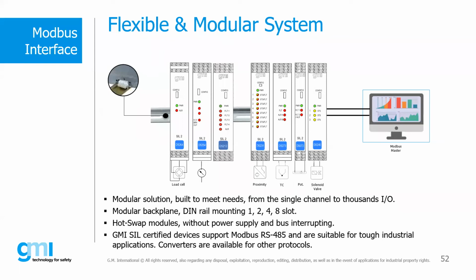The main reason for such high use of Modbus compared to other communication protocols is that it was designed with industrial use in mind. It's an openly published and royalty-free protocol, easy to install and maintain, and it moves raw bits and words without placing many restrictions on producers. Modbus allows communication between different devices connected to the same network, for example a system that measures temperature and humidity and communicates the result to a computer. Modbus is often used to connect a supervisor computer with a remote terminal unit, RTU, in a supervisory control and data acquisition system, SCADA.